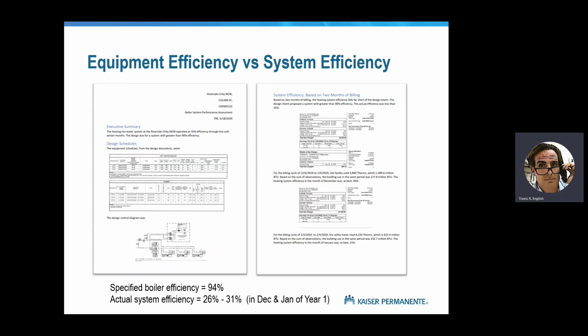And right away, we opened this building. In the first 2 months, we could tell the natural gas was way off. So we checked it for December and January of the first year of operation. This is the winter time, brand new building, brand new boiler, 94% efficient, most expensive boiler money can buy. The system efficiency was 30%. I kind of love this report because it teaches a valuable lesson. Design engineers are sometimes fooled by this notion: hey, if I specify a 94% efficient boiler, then I'm done. And that is 100% false.